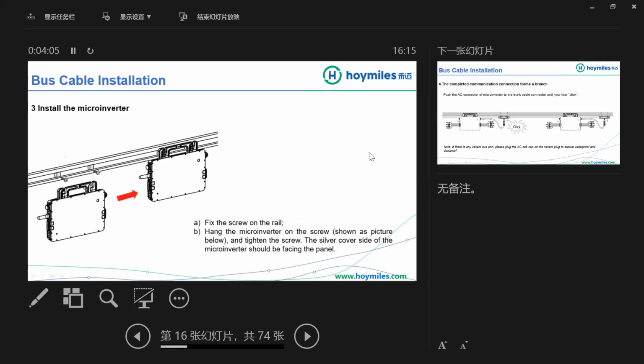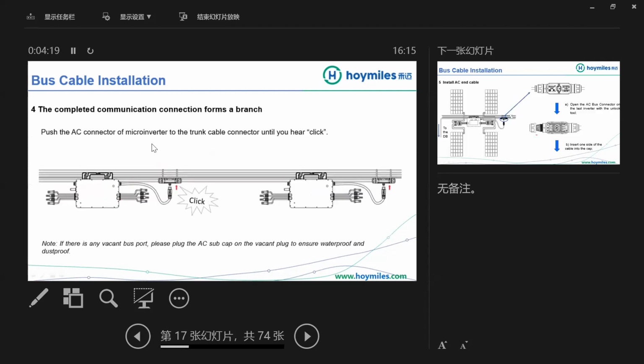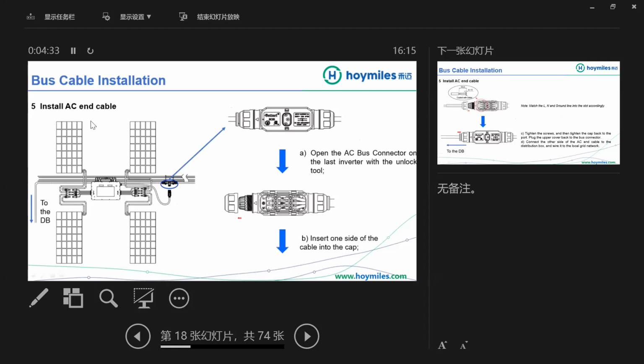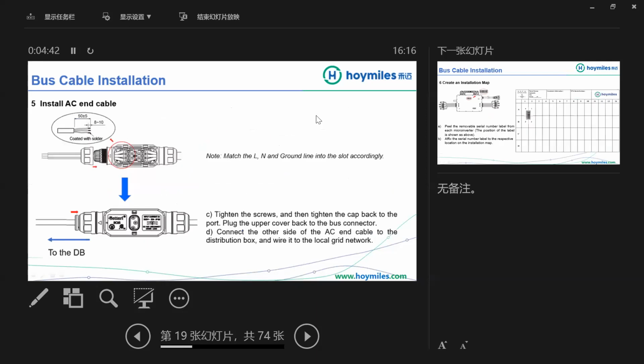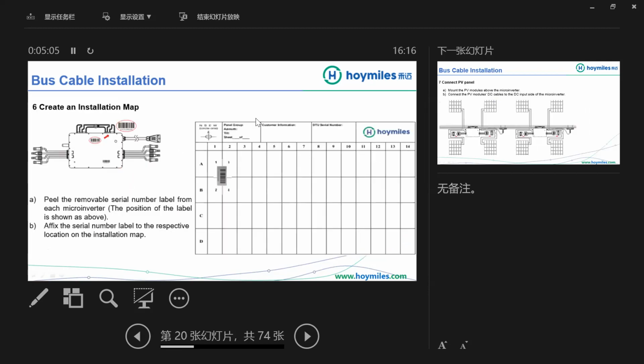Then install the microinverter. Fix the screw on the rail, hang the microinverter on the screw and tighten the screw. As we can see, the silver cover side of the microinverter should face up. Then push the AC connector of the microinverter to the trunk cable connector. If the connection is good, you will hear a click sound. Then to install the AC end cable, open the AC bus connector on the last inverter with the unlock tool and insert one side of the cable into the cap. Tighten the screws and then tighten the cap back to the port. Plug the upper cover back to the bus connector. Connect the other side of the AC end cable to the distribution box and wire it to the local grid network. It is noted to match the live, neutral and ground line into the slot accordingly. Then create an installation map. Peel the removable serial number label from each microinverter.